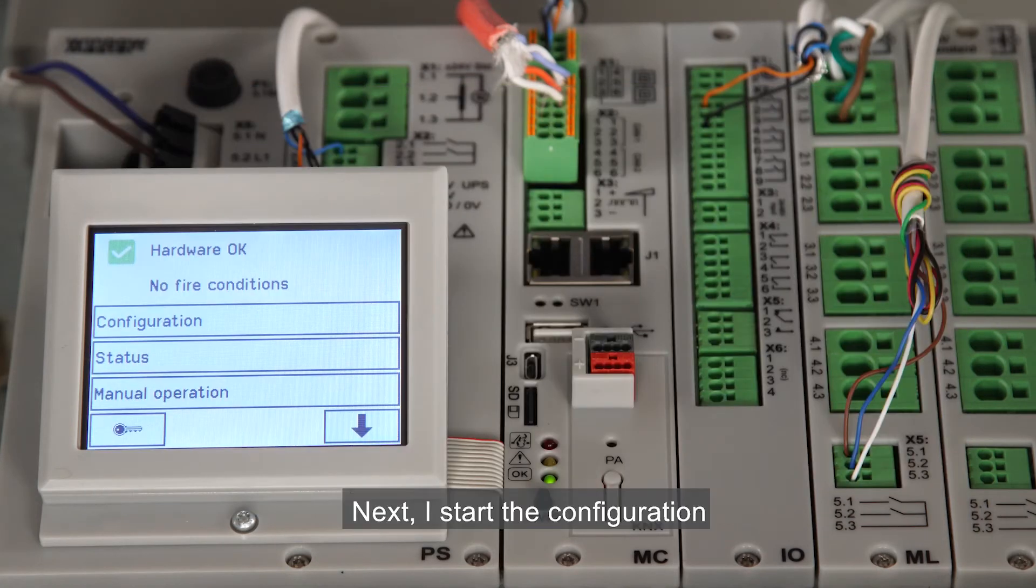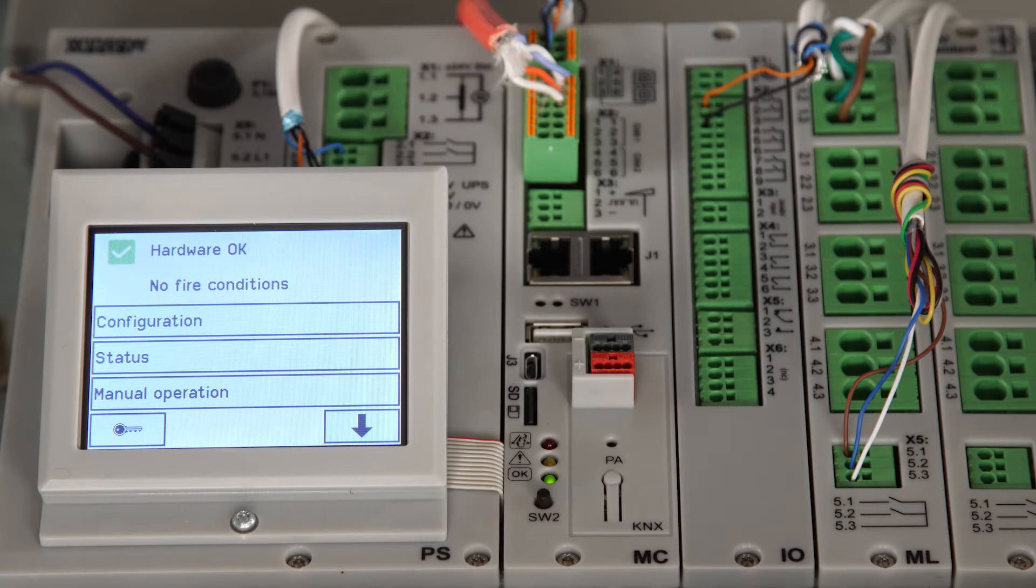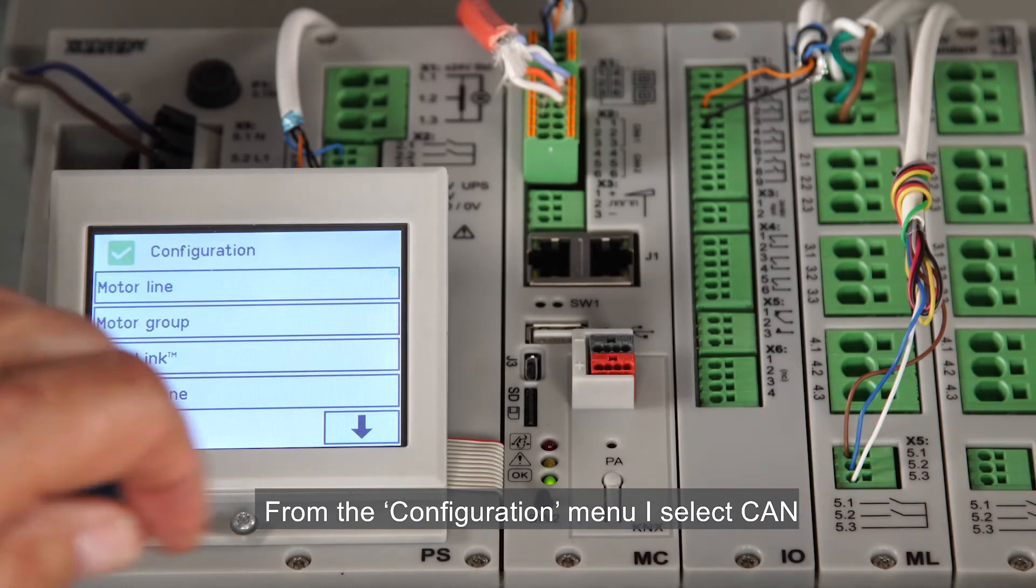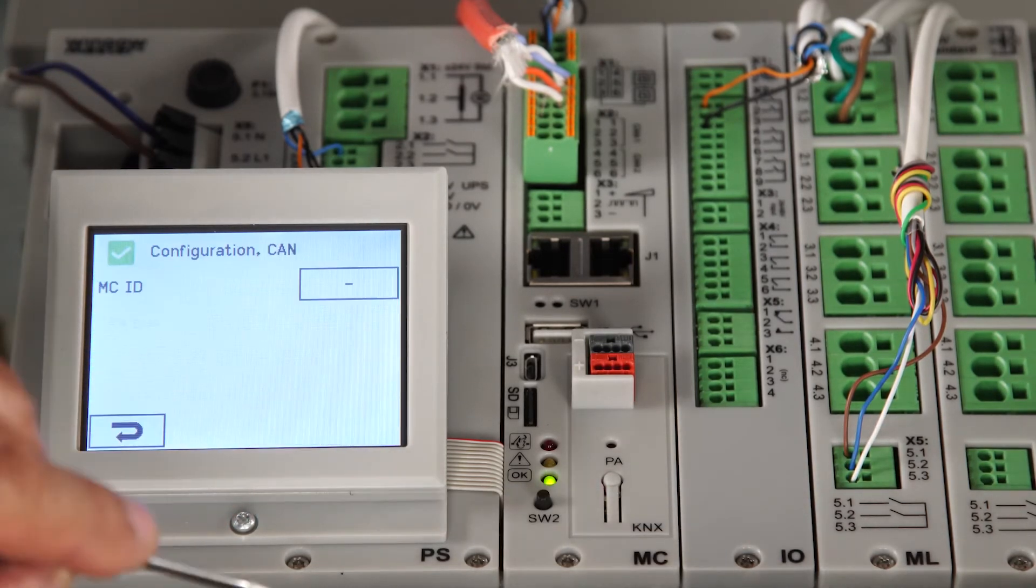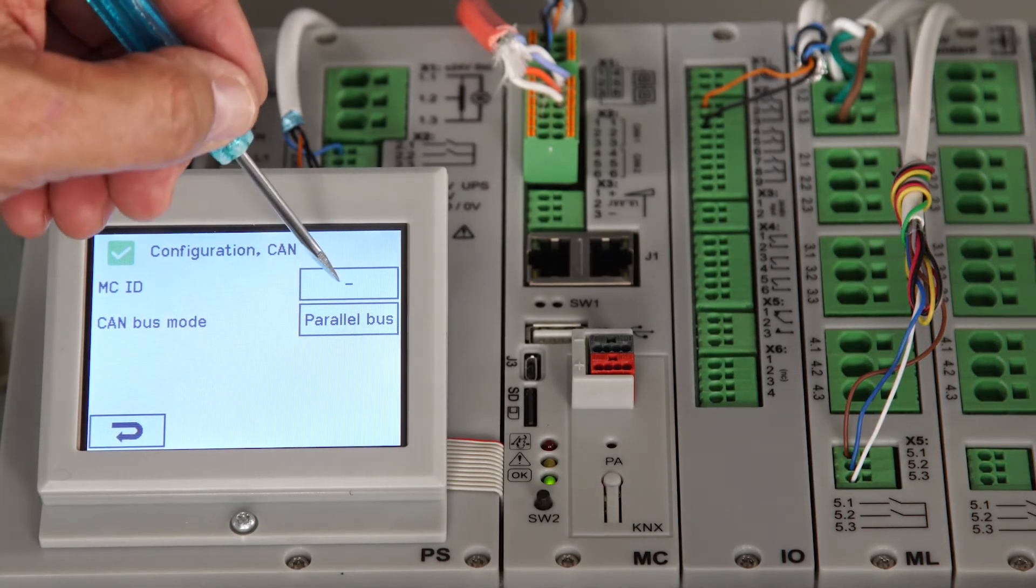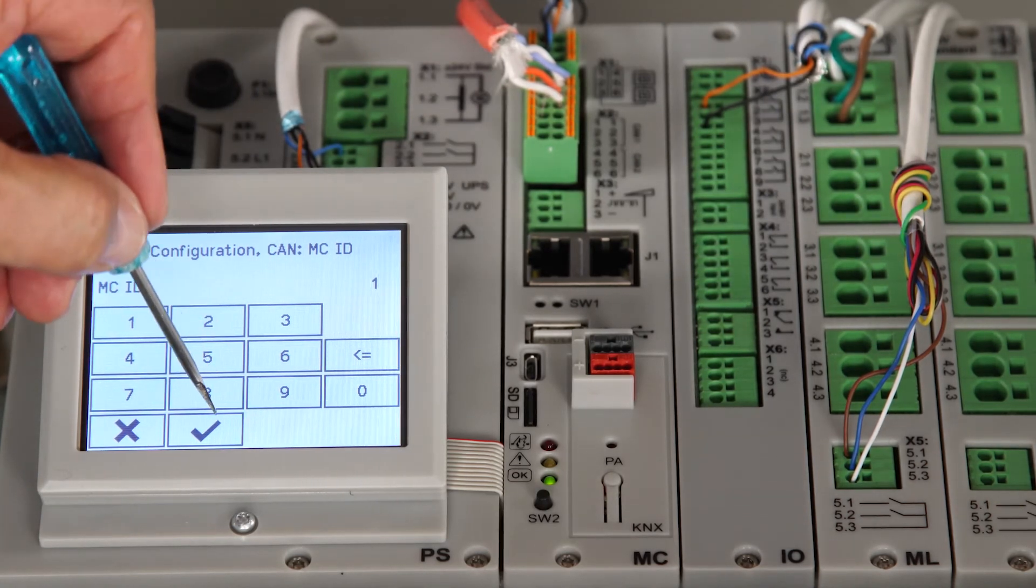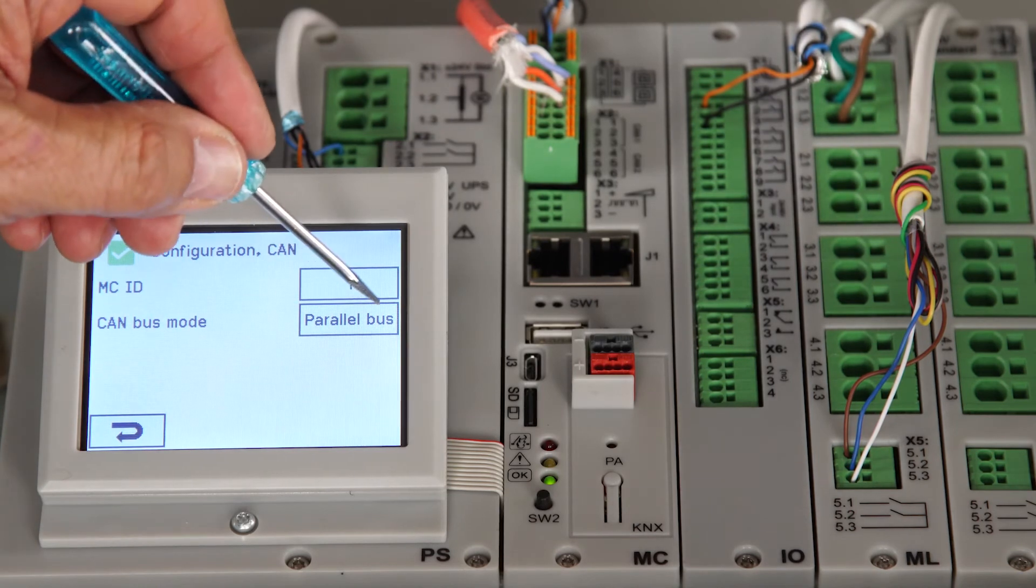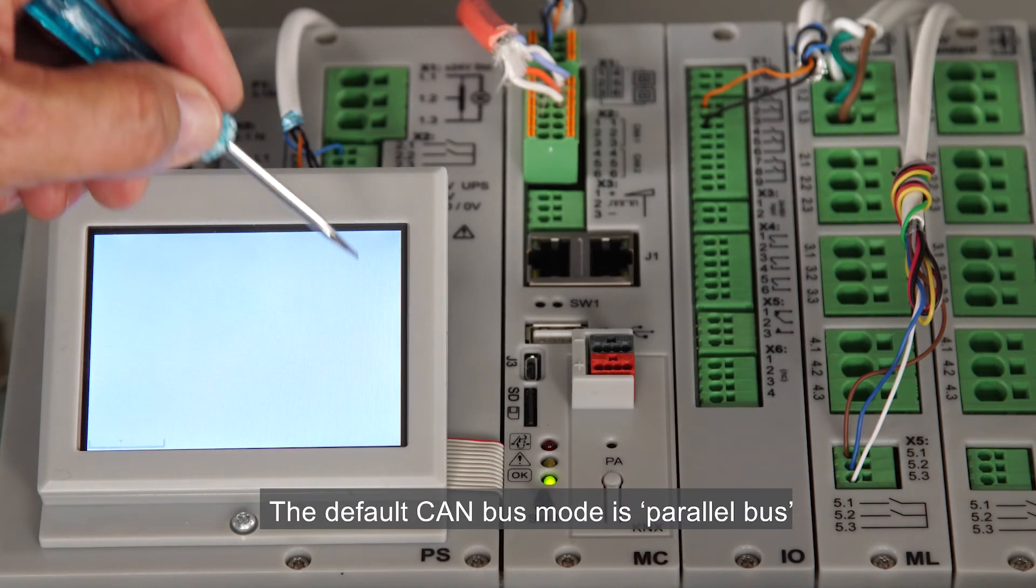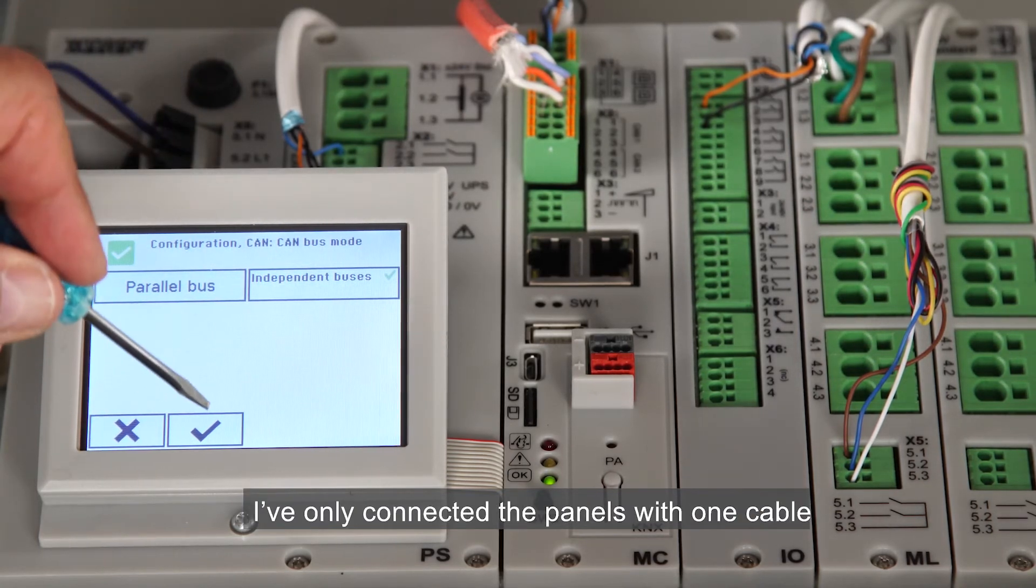Next, I start the configuration. The first thing to do is to assign CAN bus IDs to the panels. I do it first on the master panel. From the configuration menu, I select CAN and I'll insert an ID. The default CAN bus mode is parallel bus, which I need to change because I've only connected the panels with one cable.